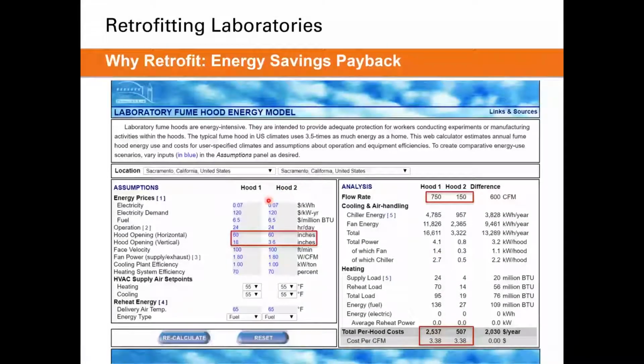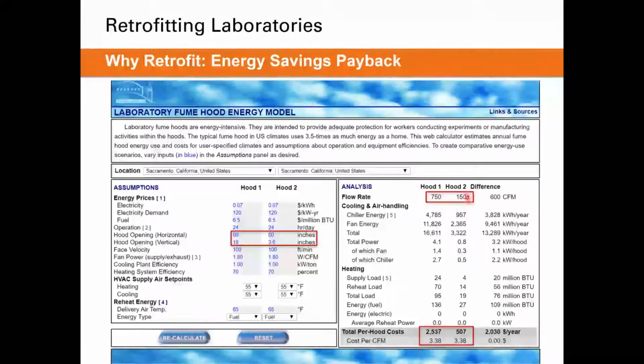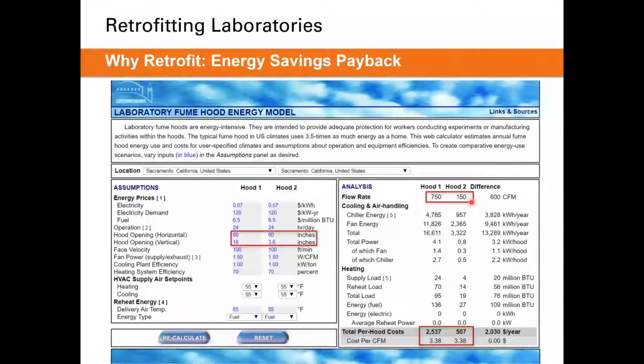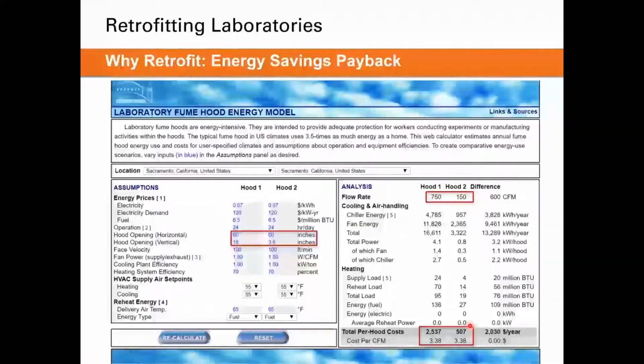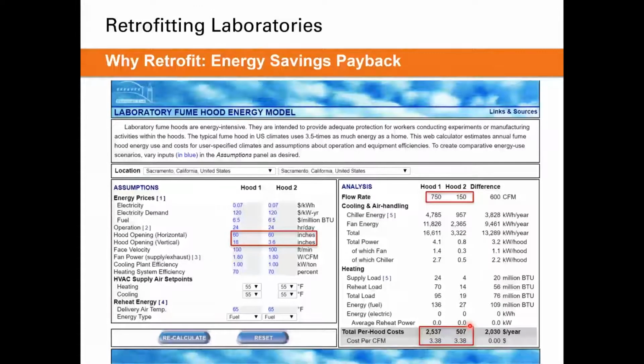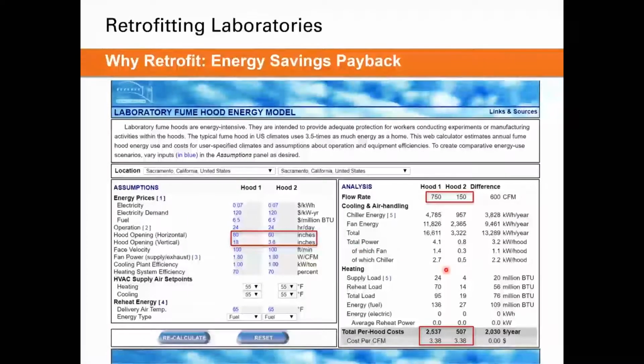So in this second page, I've put in the sash height in inches that would give me my calculated minimum flow rate that I need when this hood is in its minimum position. So that ended up being 150 CFM. So you can see that if we use hood 1 as the CV hood example, it would always be exhausting 750, and that would be a total cost per year of $2,500. But if we were able to close and vary that CFM through the hood, it can go down to $500 per year. So I know that this isn't a really realistic example exactly, because we're not going to have our hood closed 100% of the time.